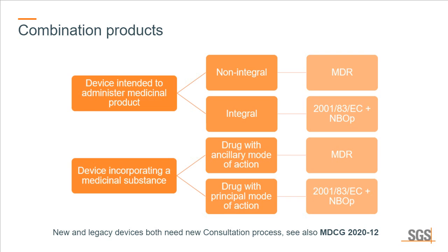And new and legacy devices both need a new consultation process. That means that even if such a combination product had the CE marking or was put on the EU market legally under the MDD, and you had performed the necessary consultation process, that device will need a new consultation process under the MDR if you want to keep selling it. And there's an MDCG guideline 2020-12 that talks about this.